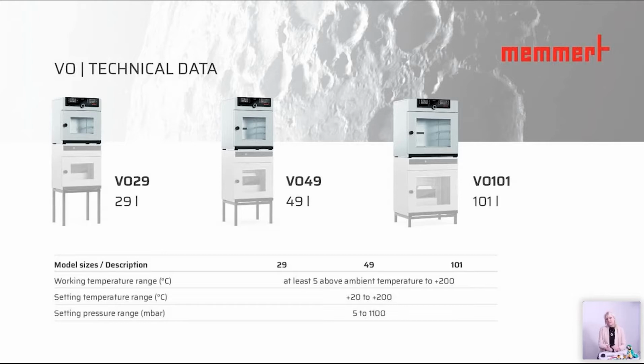But now you say, I have an application, but I actually need a little bit lower than 5 millibar. You will be lucky. It's also possible because we can set low on the vacuum oven, on the digital controller. So that means that it goes down as low as possible. And this depends on the pump which is going to be used. The pump we are offering here, you can go down to 2 millibar. So that means you set on your vacuum oven low.